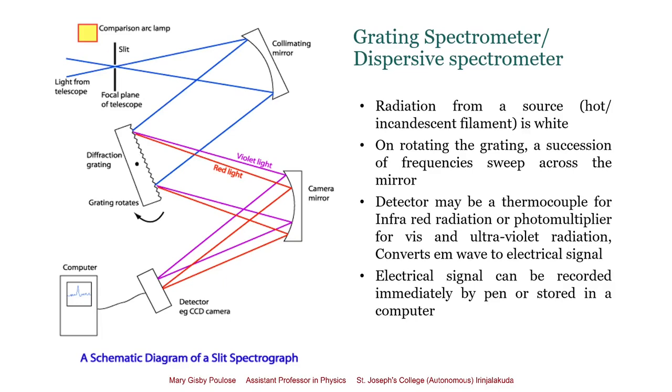The grating separates that light into its component colors. So these component wavelengths are produced by the diffracting element. By rotating the grating, I can select which wavelength falls on this mirror. So wavelength tuning is produced by rotation of the grating. Now this mirror focuses the incident wavelength upon a detector, and that output can be recorded into a computer or onto a graph.